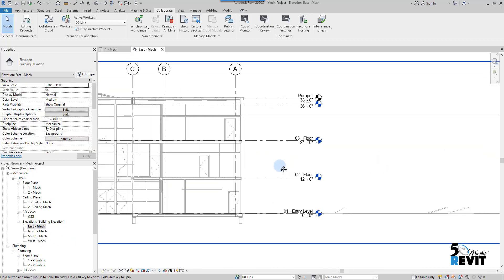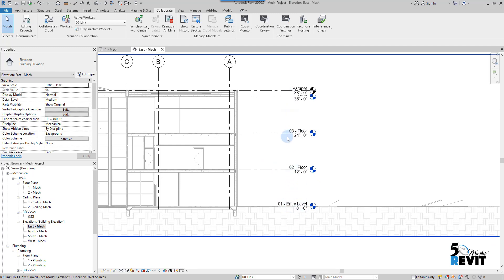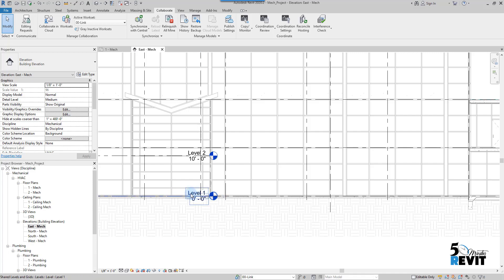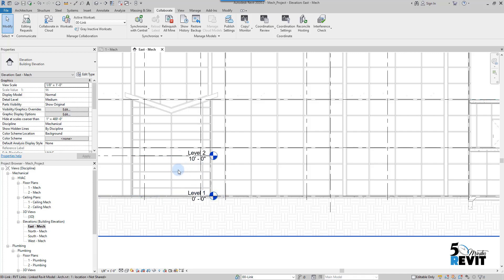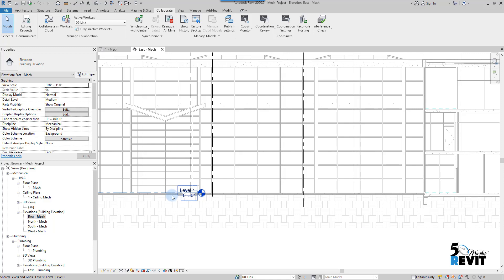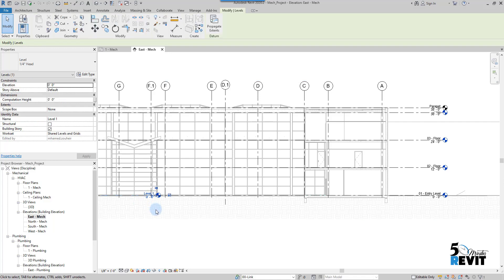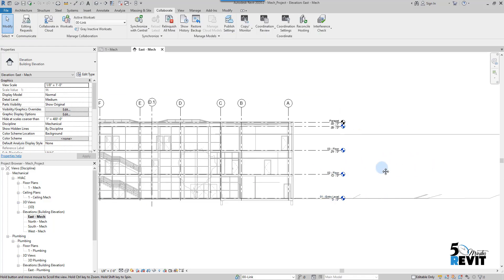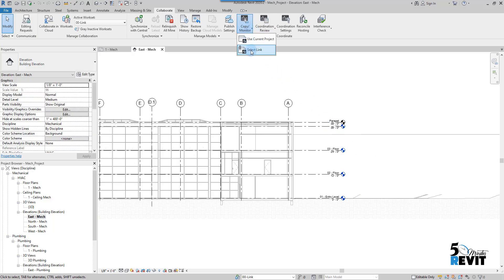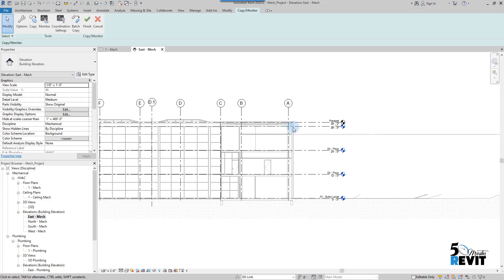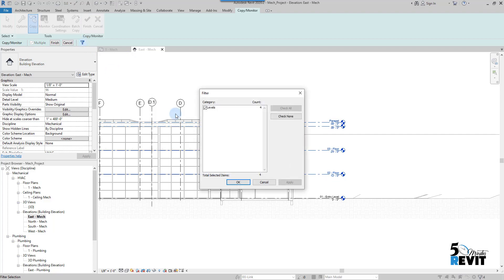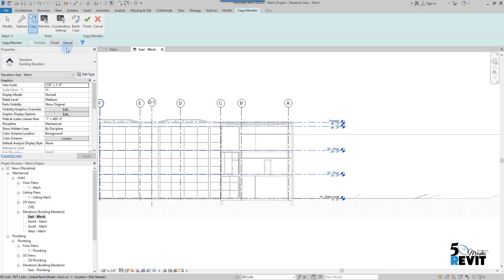I will do the same for levels. I go to East Elevation and I can see the levels from the link. I also have levels that came with my template — I can delete those. I keep one because Revit doesn't allow you to delete all levels; you need at least one level in the project. Now I go to Copy Monitor, select the link, click Copy Multiple, select all my levels, and use the filter to make sure only levels are selected. Then I click Finish.